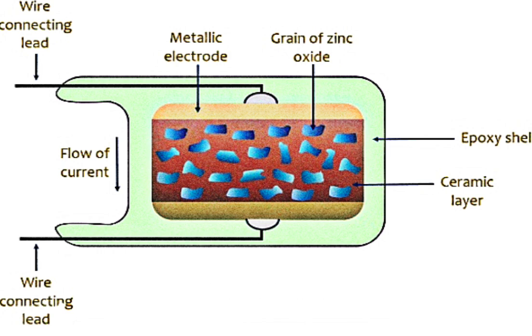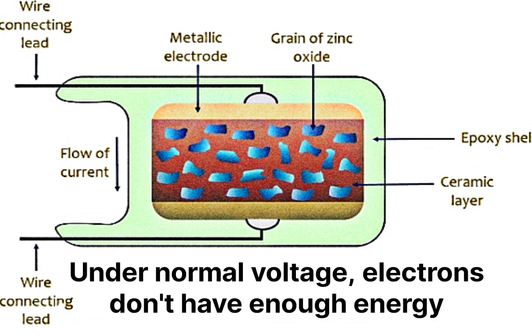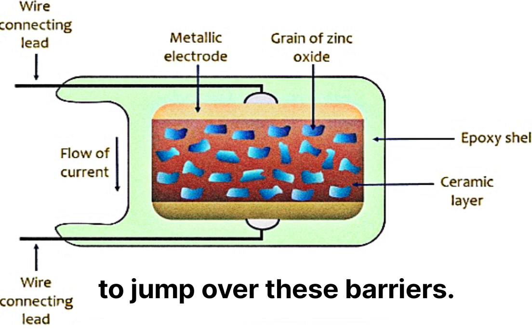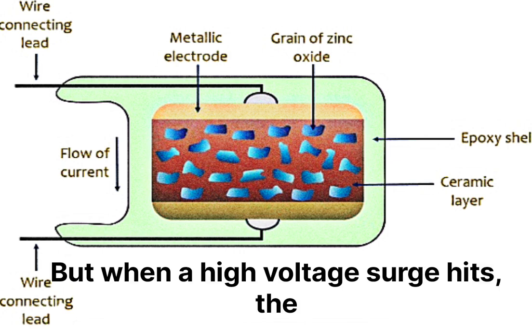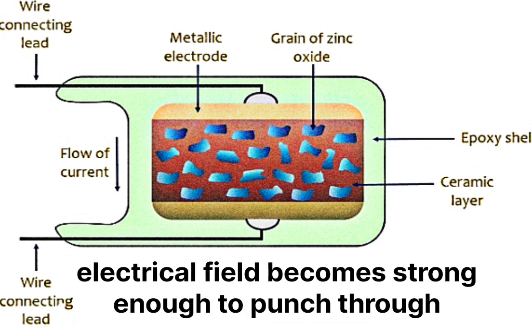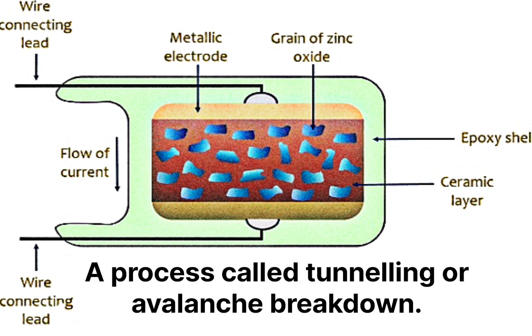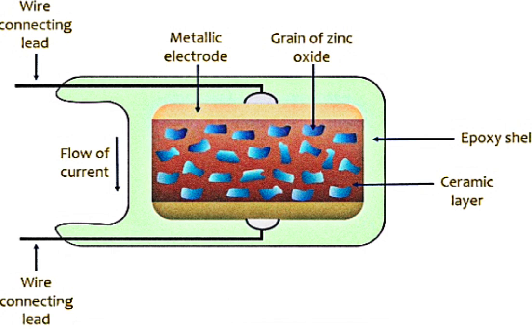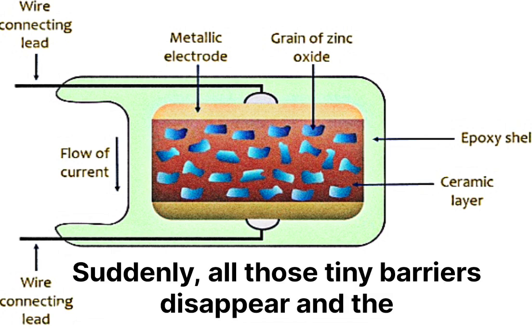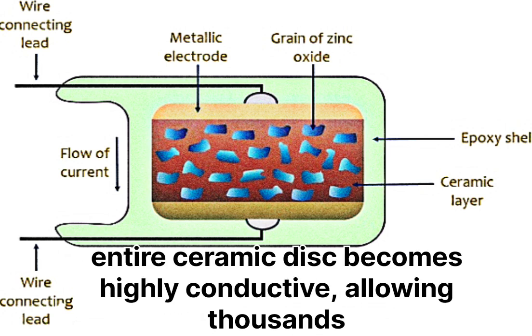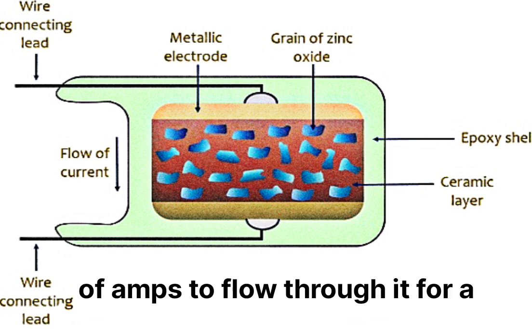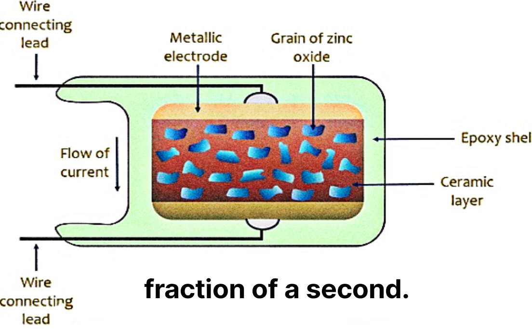The breakdown. Under normal voltage, electrons don't have enough energy to jump over these barriers. But when a high voltage surge hits, the electrical field becomes strong enough to punch through these barriers, a process called tunneling or avalanche breakdown. Conduction. Suddenly, all those tiny barriers disappear, and the entire ceramic disc becomes highly conductive, allowing thousands of amps to flow through it for a fraction of a second.